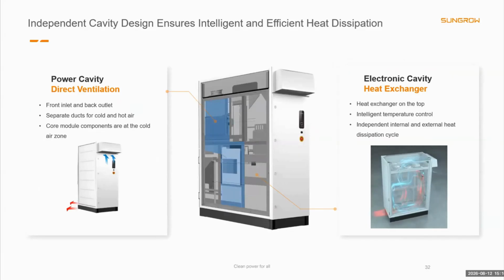The inverter separates the power cavity from the electronic cavity. The power cavity uses direct ventilation, while the electronic cavity uses an independent heat exchanger. This allows efficient cooling while protecting sensitive electronics from dust and moisture.